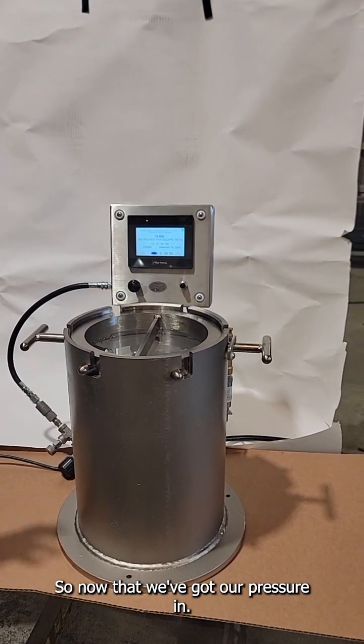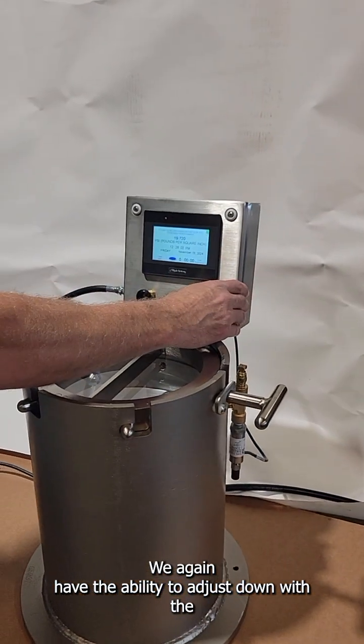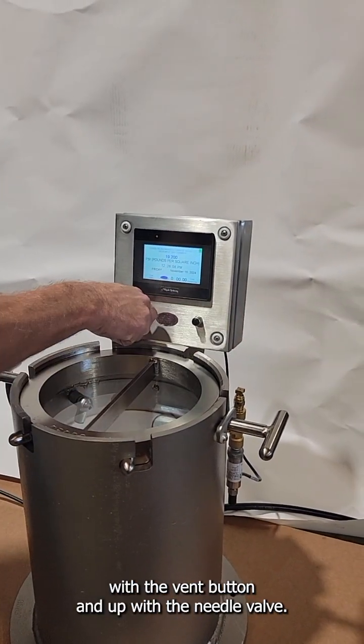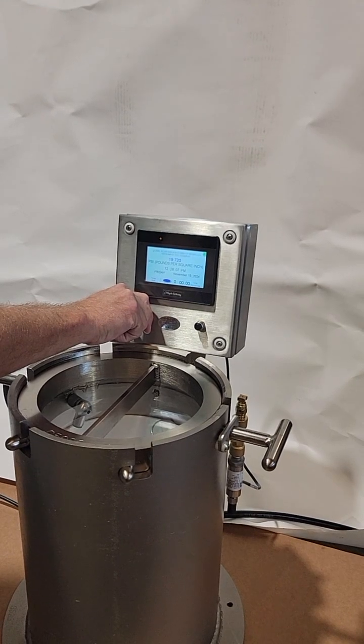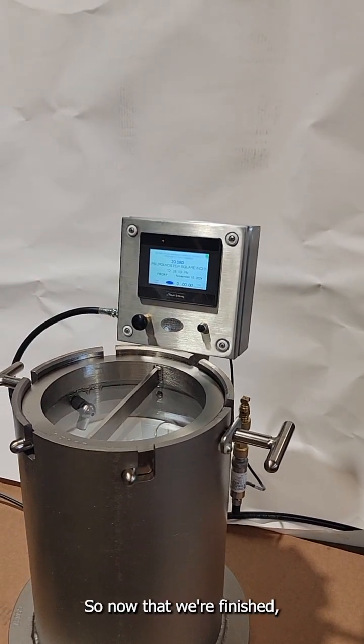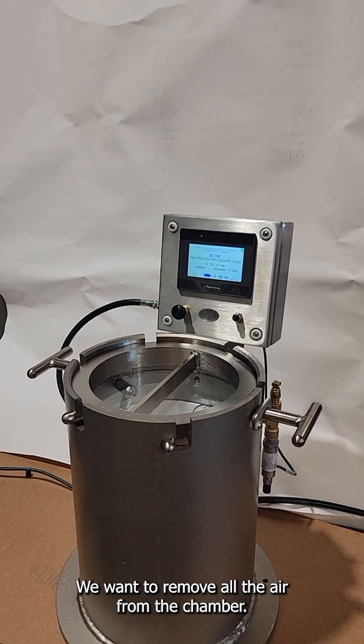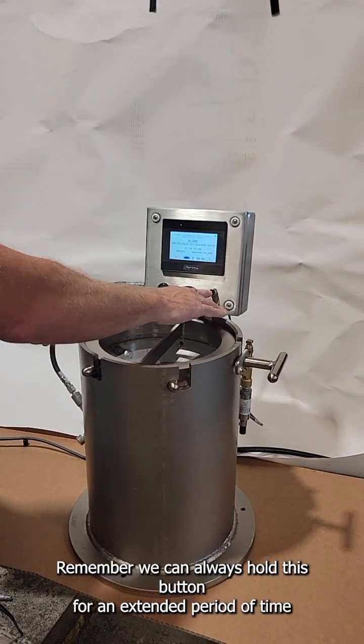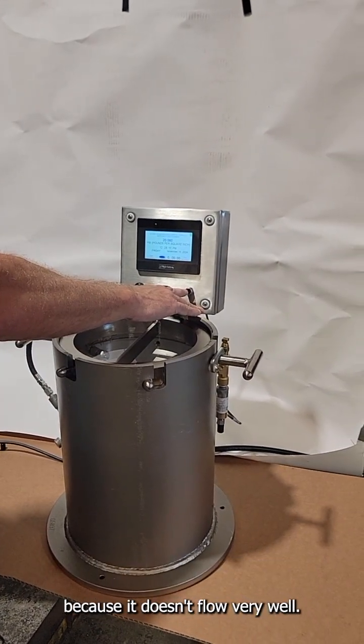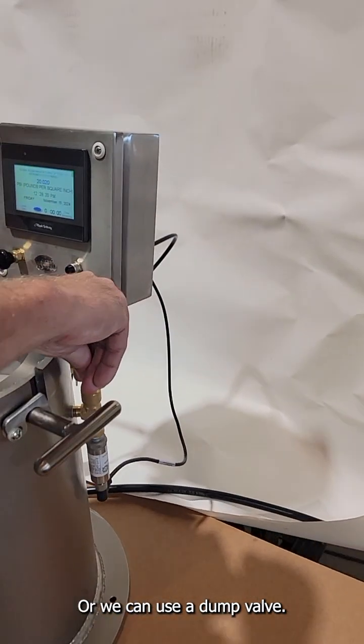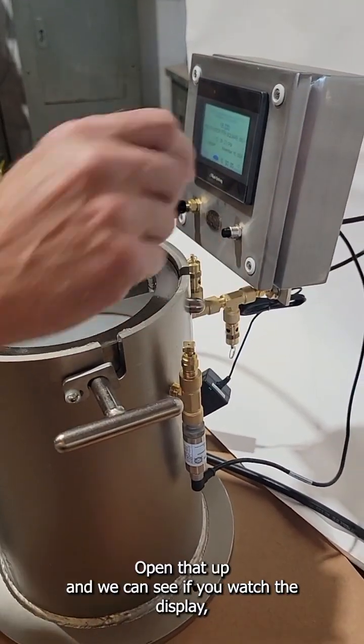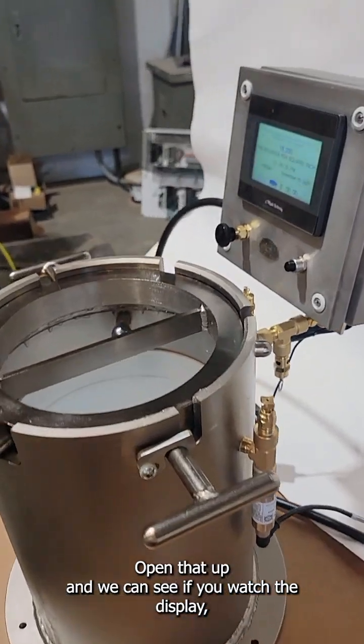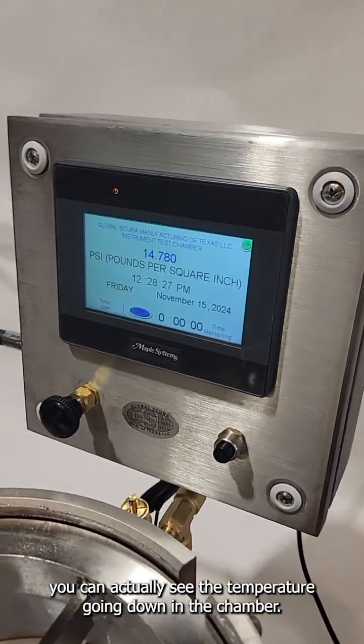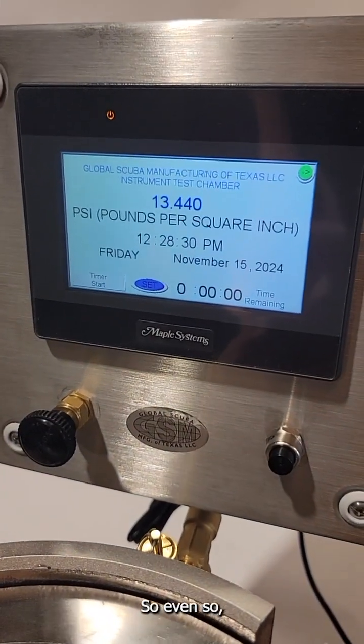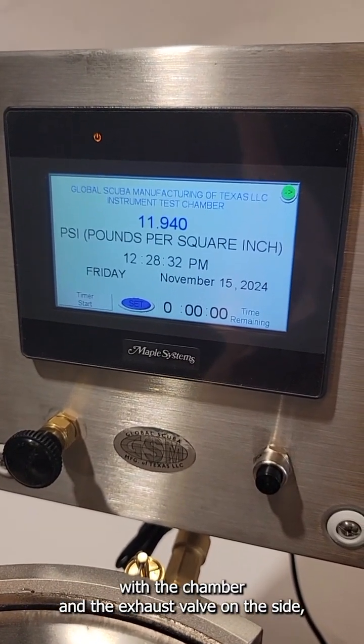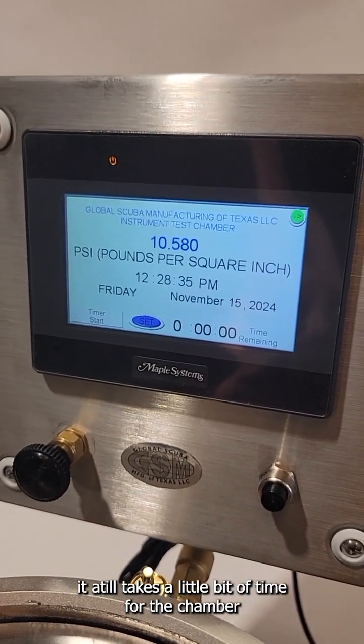So now that we've got our pressure in, we again have the ability to adjust down with the vent button and up with the needle valve. So now that we're finished, we want to remove all the air from the chamber. Remember, we can always hold this button for an extended period of time because it doesn't flow very well, or we can use the dump valve. Open that up, and if you watch the display, you can actually see the pressure going down in the chamber. Even with the exhaust valve on the side, it still takes a little bit of time for the chamber to empty out.